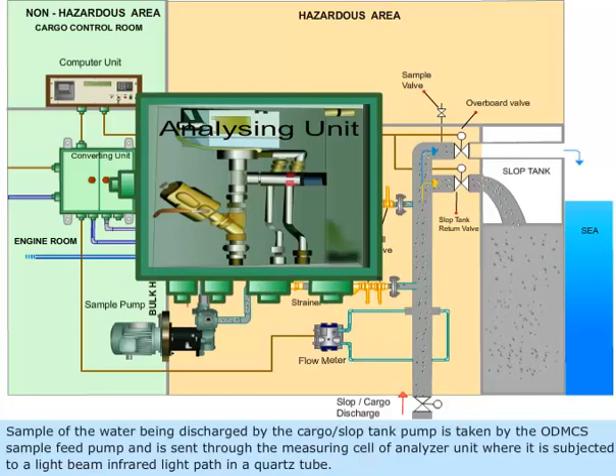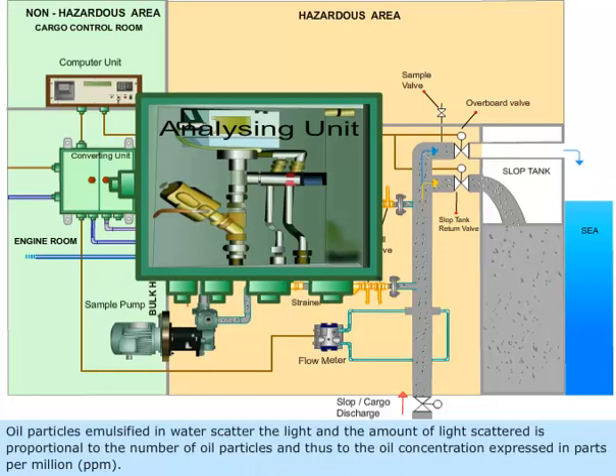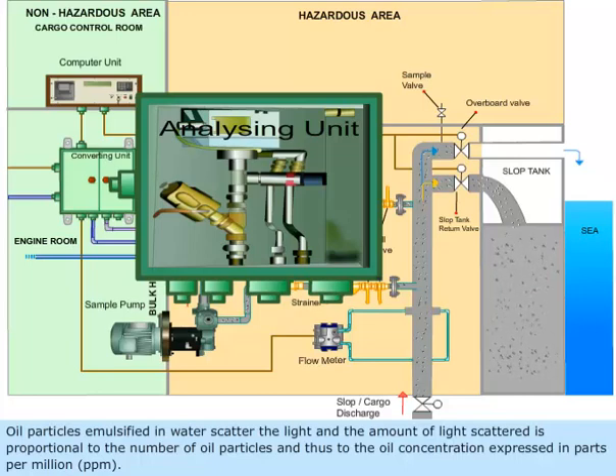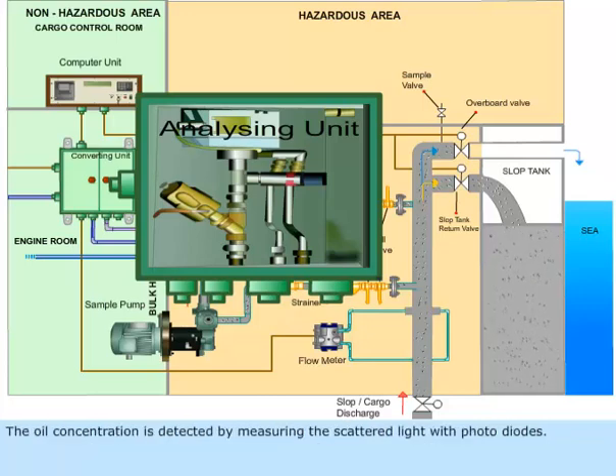In the measuring cell, the sample is subjected to an infrared light beam in a quartz tube. Oil particles emulsified in water scatter the light, and the amount of light scattered is proportional to the number of oil particles and thus to the oil concentration expressed in parts per million or ppm. The oil concentration is detected by measuring the scattered light with photodiodes.